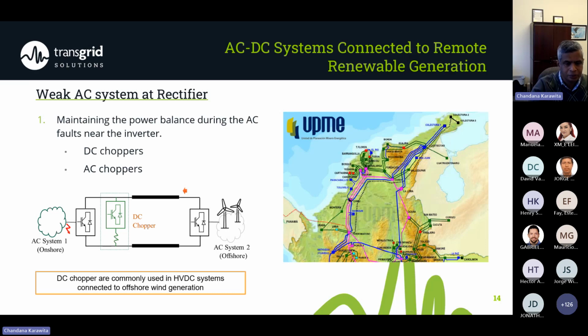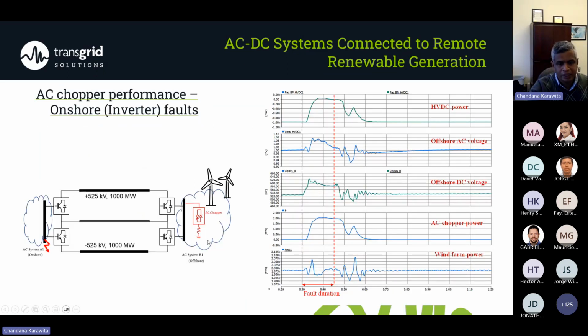But in recent projects, especially onshore renewable generation, similar to the Colombia system, we propose AC choppers. Instead of the DC chopper, we connect a chopper on the AC side, and this is a much cheaper solution. A DC chopper is like an HVDC converter valve; we usually use an MMC converter for it. With an AC chopper, we can use thyristor-based AC choppers, and the solution is much cheaper compared to the DC chopper. These are some of the results we obtained for a fault on the onshore system. We can operate the AC chopper to keep the system stable during this disturbance.